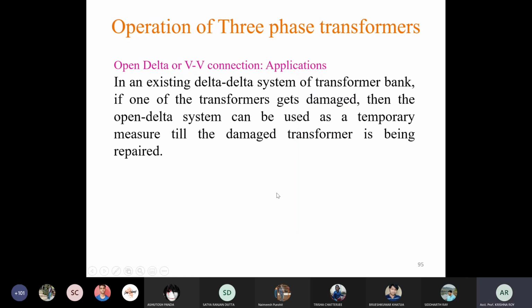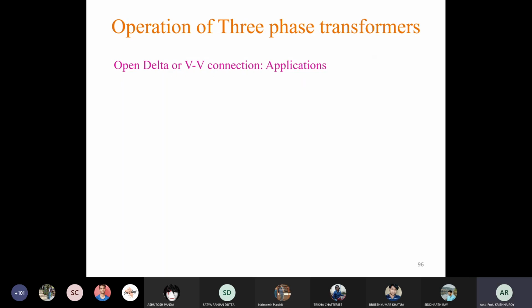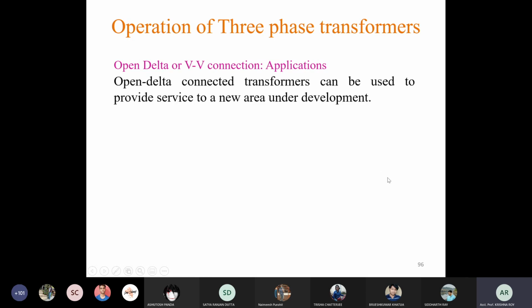So now the applications. What are the applications of this open delta or VV connection? It is very simple. If any one of the delta-delta connected transformers gets damaged, we can still be operative. That means we will be able to supply the load for the time being with this open delta connected system till the damaged transformer is repaired. Another very important application is that this open delta connected transformer can be used to provide service to a new area under development.